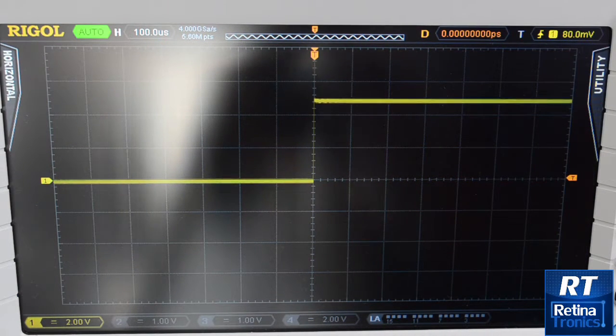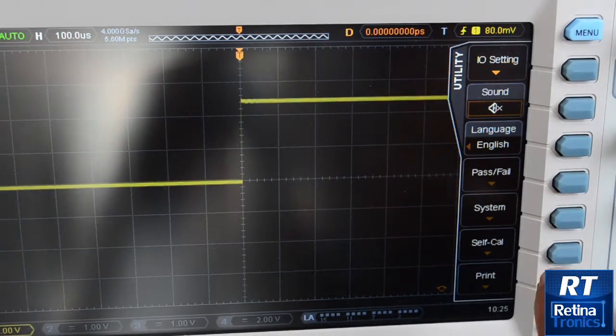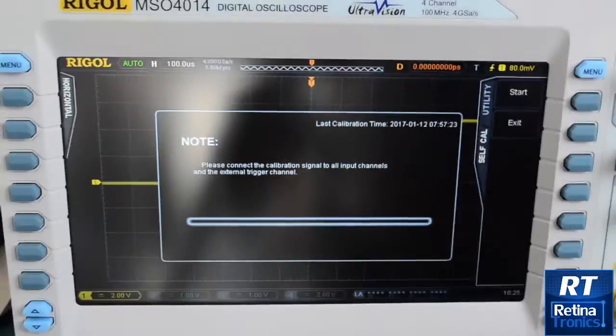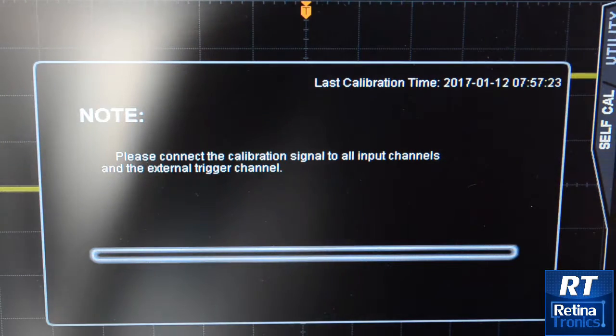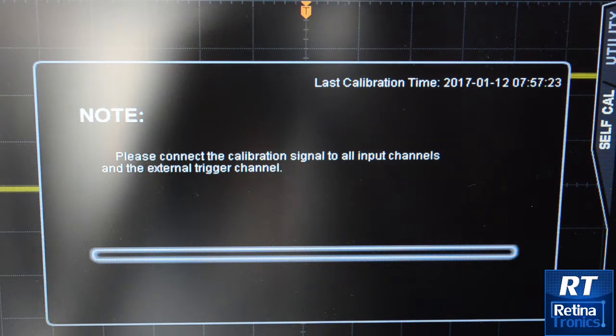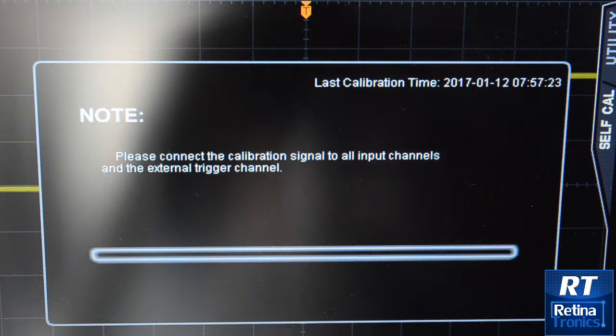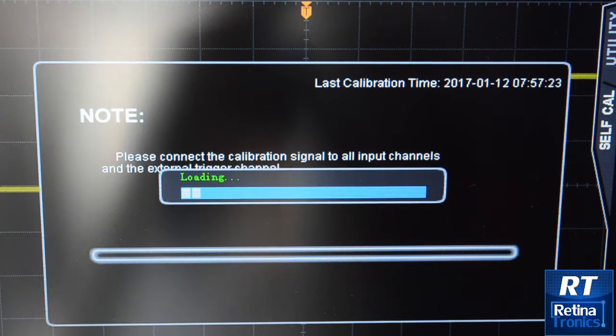What you have to do is you go to utility and press the self calibration button over here, and then the scope will ask you to connect the calibration signal to all input channels and the external input trigger. So it asks you to connect the calibration signal to all the 5 channels of the scope, and press start.